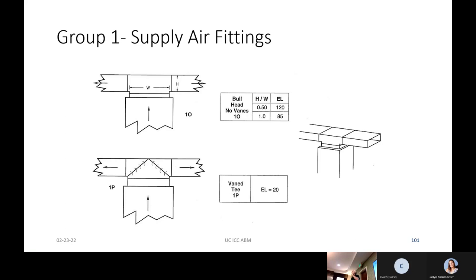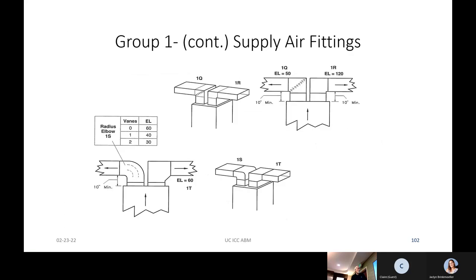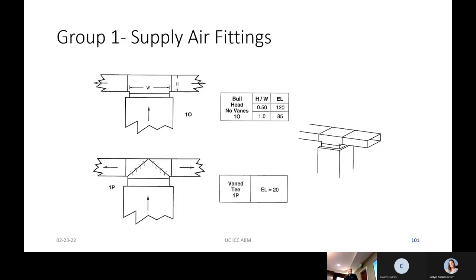When I was early in my HVAC career, my boss took me out to install an air conditioner up in Pepperwood. He said this duct system has some problems. We were adding air conditioning. He said we're going to put a bigger motor on it. It had just a square elbow, and all the air went one direction. It really doesn't matter if it's going two directions or one direction. If you have to make that sharp 90 right off the furnace, it's going to be 120 feet of length. Those are olden days, belt drive days.